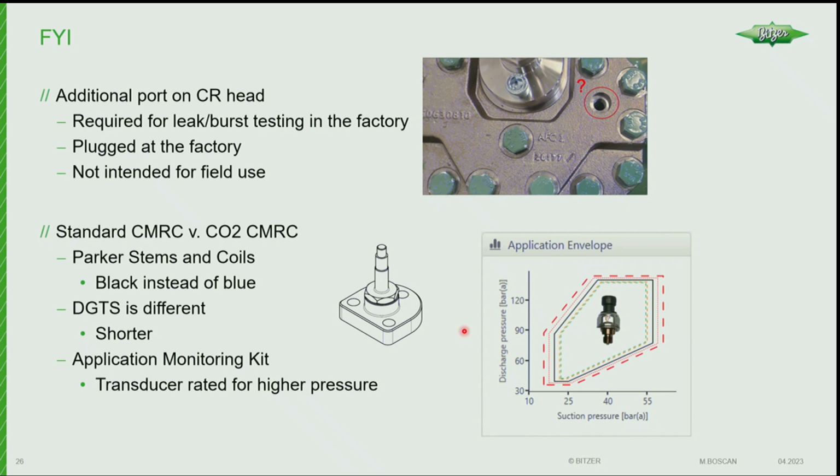Since I've been in BITZER, not CO2 but HFC versions, we've burst 2 compressors. Both ended up being fissures and small cracks in the castings, and it shakes the whole building, and it's loud. But the HFC we put in a barrel, it almost looks like a wine barrel. It's wood with big steel doors, and they close that off.